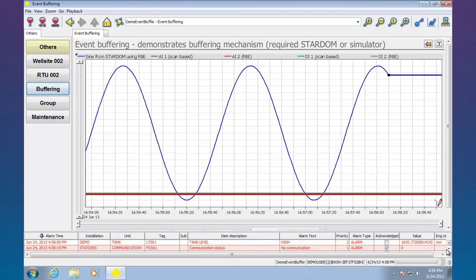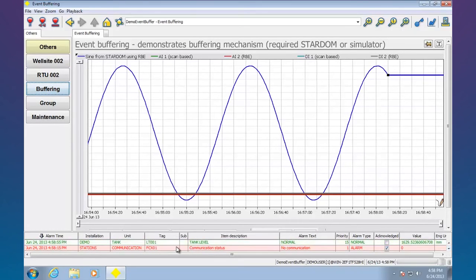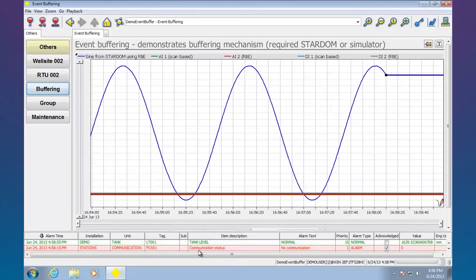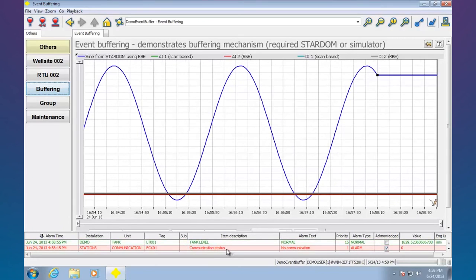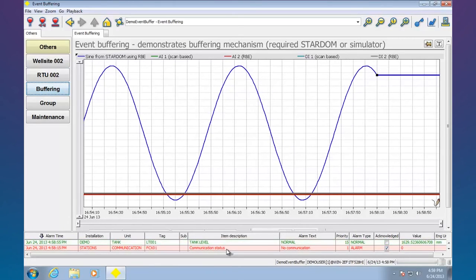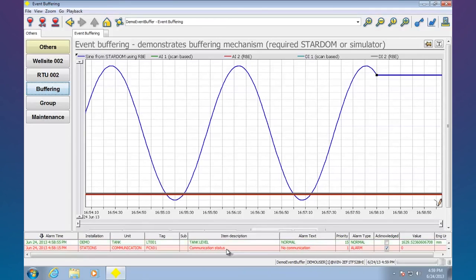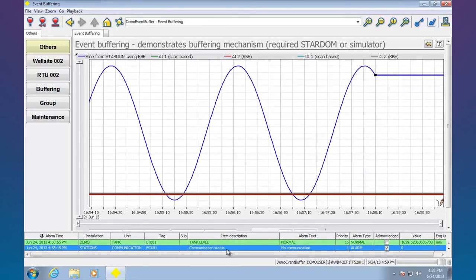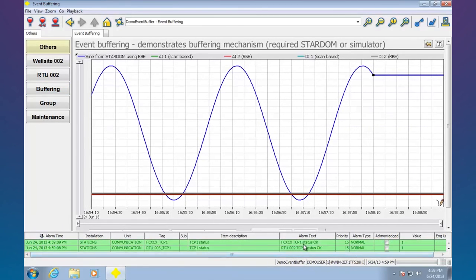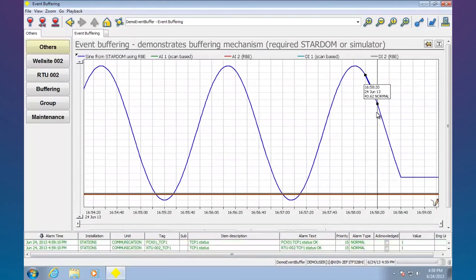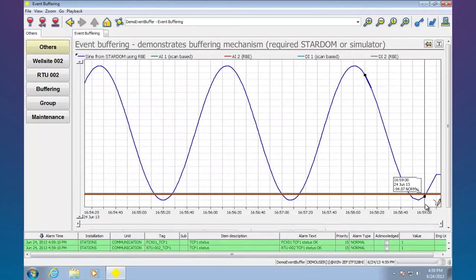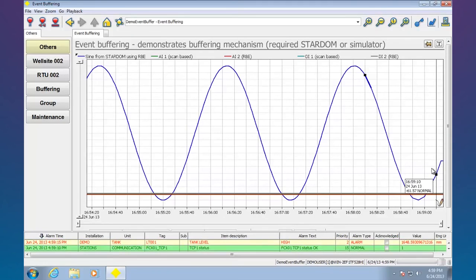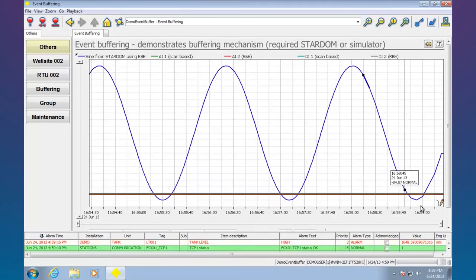So we'll just have to wait. I think any second now we should see our communication status here go green as it finds the Stardom unit is back on the network. Alright, so it now says the status is normal. And we can see the trend is getting rebuilt. So there it is. We didn't lose any data. All that data came back in.